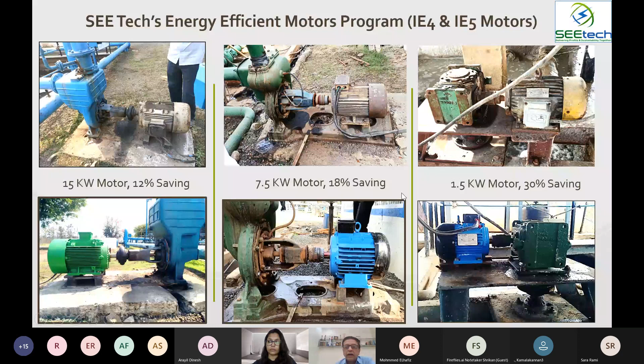Let's see further, there is a pulley drive. In this pulley drive, you can see the old motor, which was retrofitted with the energy efficient IE4 motor. The existing motor was 3.7 kilowatt, but the load was measured and it was found that the motor size could also be reduced. Size optimization is also a very important process. So here we replaced it with a 2.2 kilowatt IE4 motor.